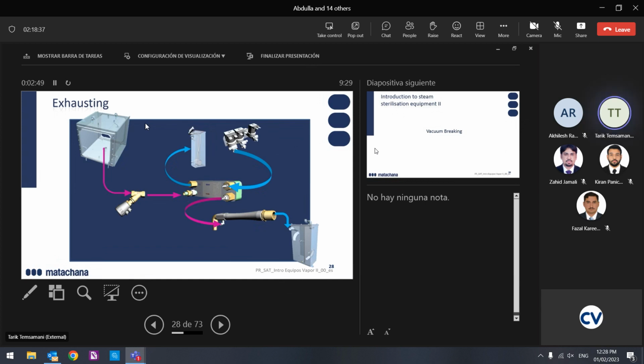And now we have another problem. When we put this line directly to the drain, no. So we take it into the steam generator tank. Normally this water goes into the steam generator and we heat it. Why not put this water in already heated? But not mixed, because this water is not RO water. This is RO water. So we put this serpentine inside this water, and the water goes through the serpentine and then to the drain. We profit from this heat to warm a little the steam generator's RO tank.